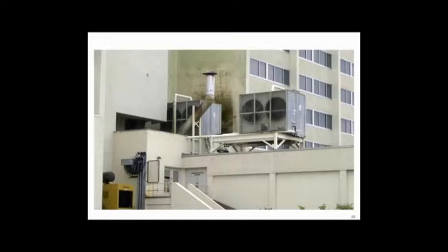Here we go with a typical example. This happens to be a hotel in Wellington, North Carolina, and we got a complaint. That tower up between the two sides of the building there, a nominal 100-ton tower, will not get you 100 tons. I wonder why. And by the way, before you forget it, the tower outside works fine. The one out in the air could get 100 tons. The one between the two walls of the building could not. Take another look at that. What is on that wall up there? You don't want to lick that wall, just picking at you.